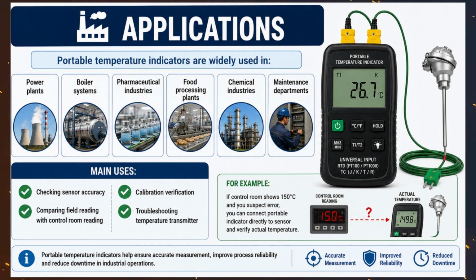Applications. Portable temperature indicators are widely used in power plants, boiler systems, pharmaceutical industries, food processing plants, chemical industries, maintenance departments. Main uses: checking sensor accuracy, comparing field reading with control room reading, calibration verification, troubleshooting temperature transmitter. For example, if control room shows 150 degrees Celsius and you suspect error, you can connect portable indicator directly to sensor and verify actual temperature.